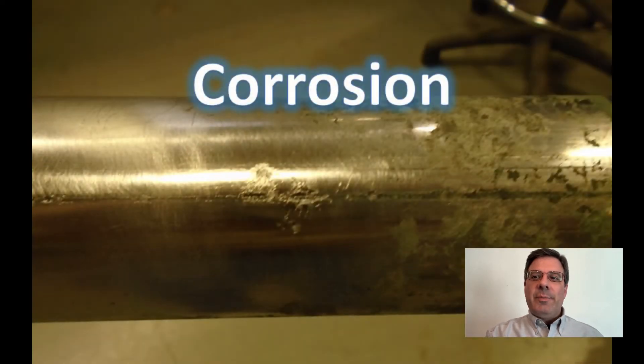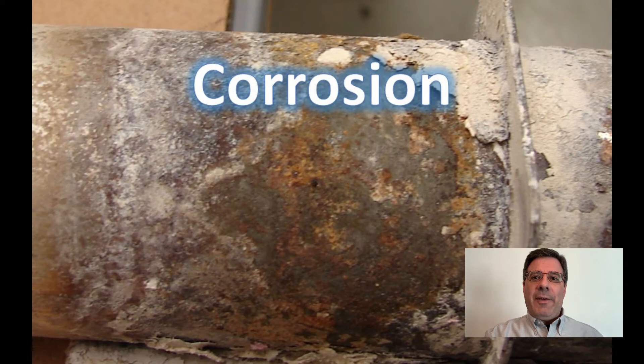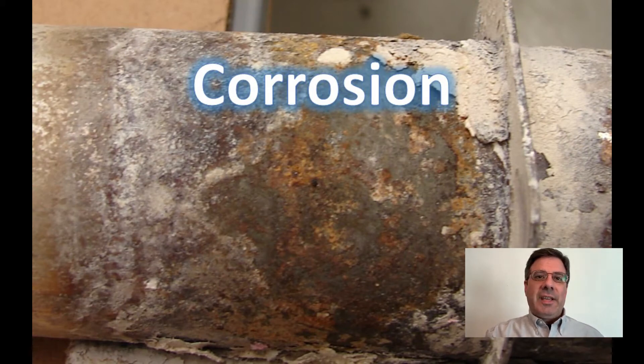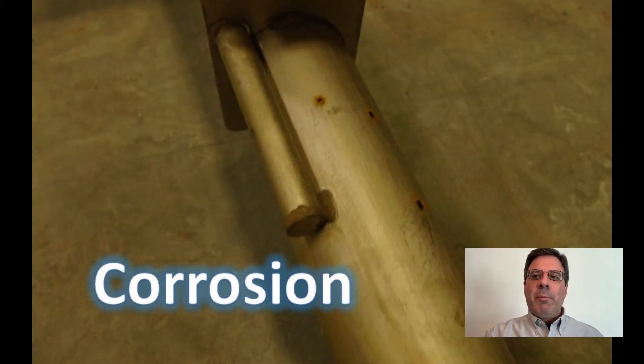The corrosion will eat away the surface material of the heater, ultimately creating holes in the sheath. Once a hole is created, liquid can immediately get inside and cause an electrical path to the grounded sheath. This will trip a ground fault device. But if left to continue, it could eventually melt holes in the heater surface and blow the fuses or trip the main breaker or disconnect.